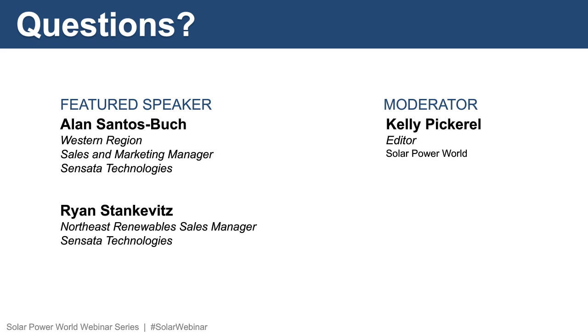Oh, thank you, Kelly. I'll take this one. Yes, the PAE will frequency shift in stages to control the output of our micro GT, but if the battery voltage should continue to rise, it will quickly drop that frequency down outside of the UL 1741 window, shutting down any grid tie inverter. So essentially, it will still work with an Enphase or an SMA or a Fronius or whatever brand you might use, but you're going to give up that regulated charging that we get using the Magnum slope with the micro GT and the PAE. You'll still protect from overcharge of the battery, but you won't get any regulation. Thus, your batteries won't be quite as happy. But if it's a retrofit, that would work just fine.